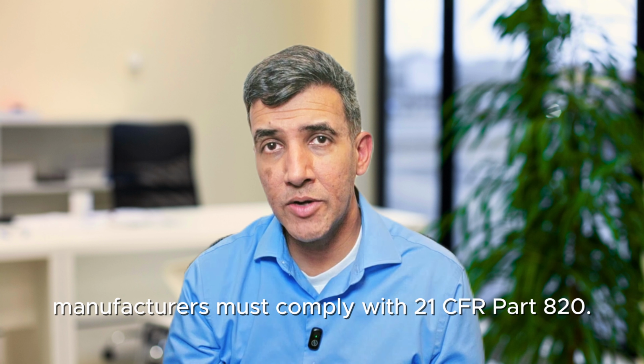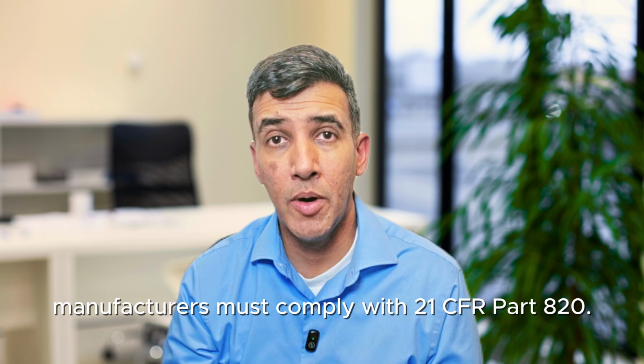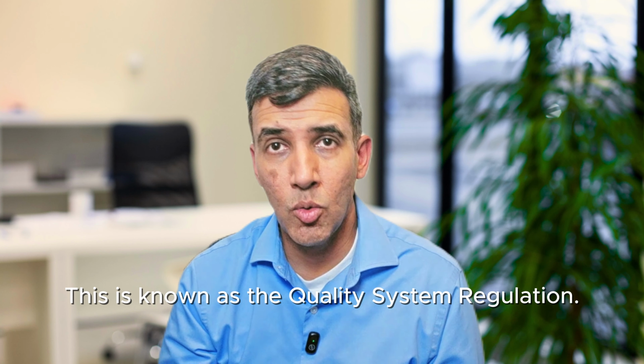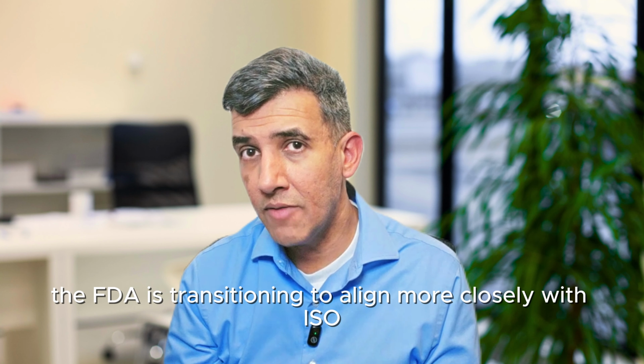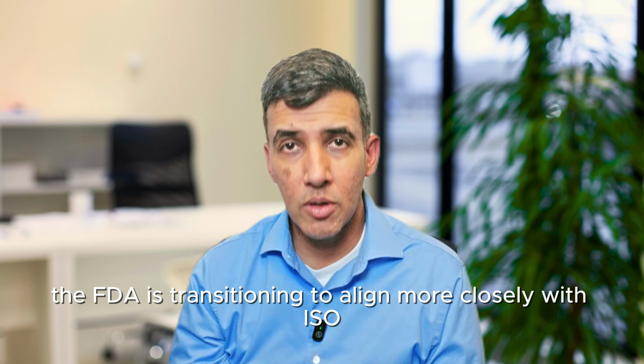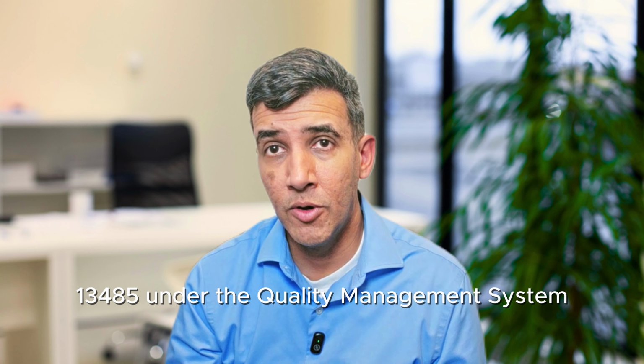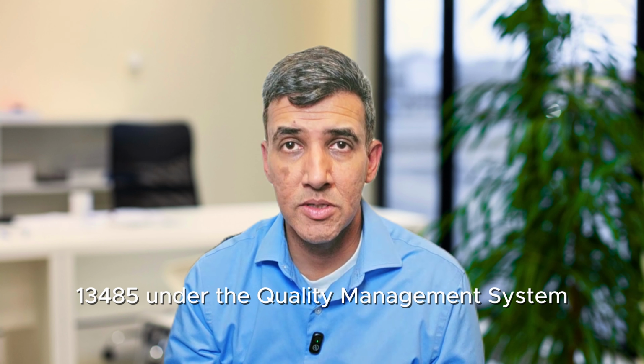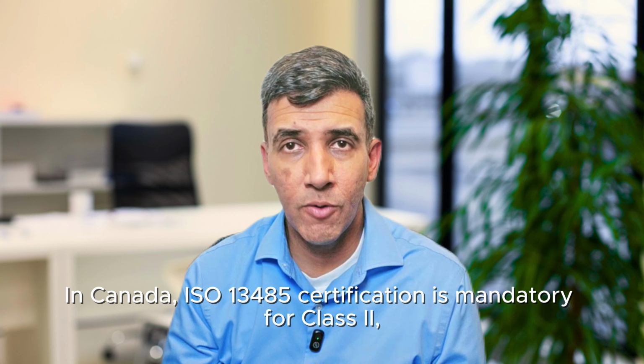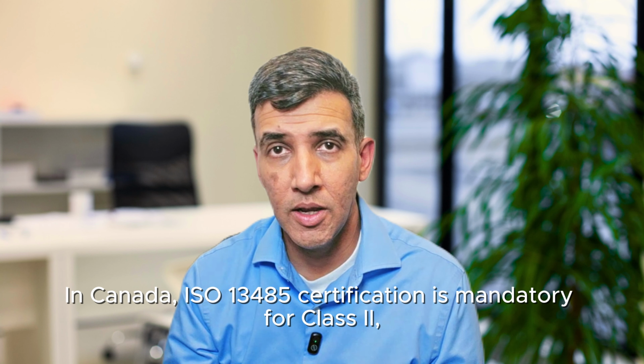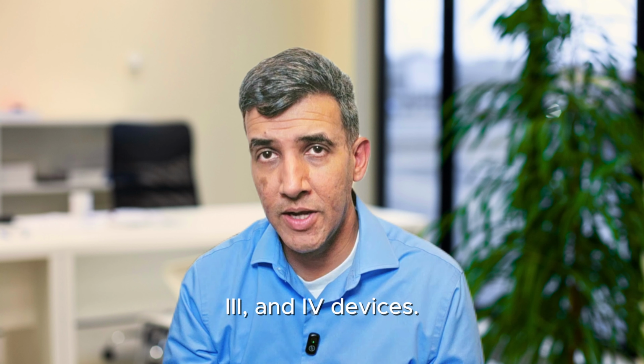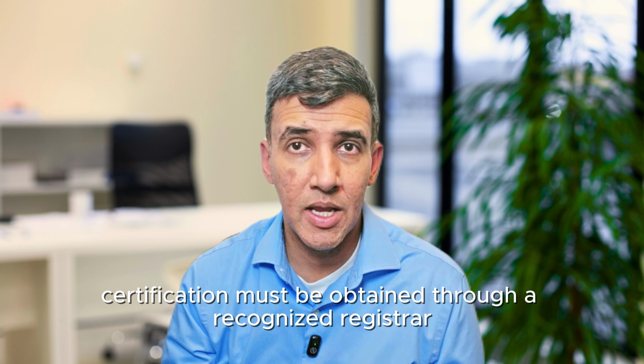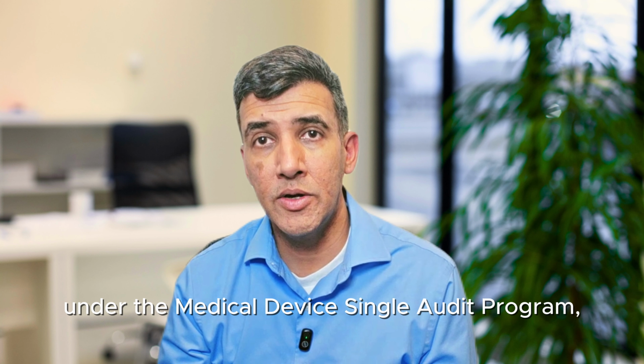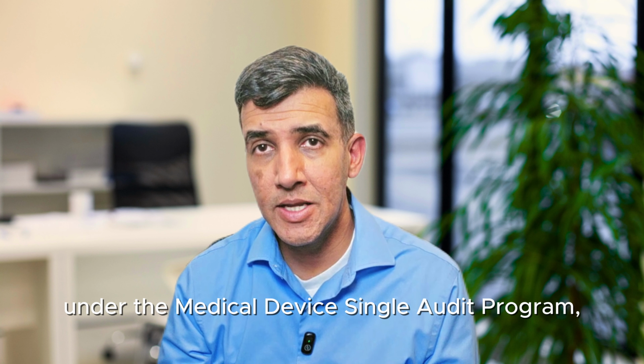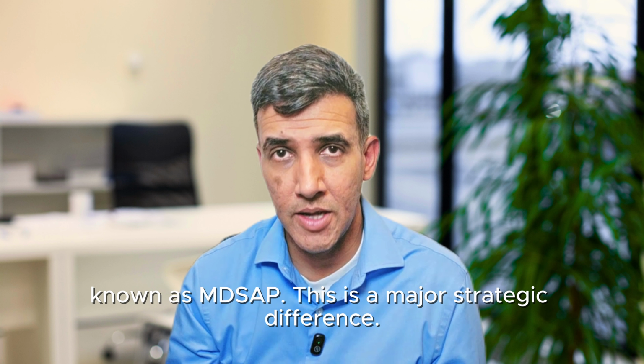In the US, manufacturers must comply with 21 CFR Part 820. This is known as the Quality System Regulation. However, the FDA is transitioning to align more closely with ISO 13485 under the Quality Management System Regulation framework. In Canada, ISO 13485 certification is mandatory for Class 2, 3, and 4 devices. Certification must be obtained through a recognized registrar under the Medical Device Single Audit Program, known as MDSAP.